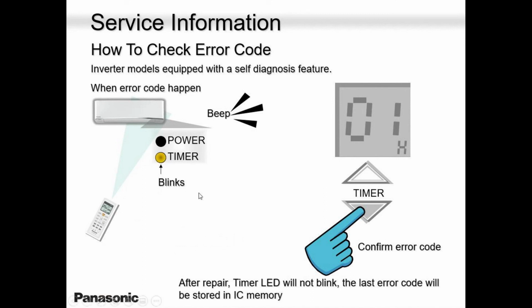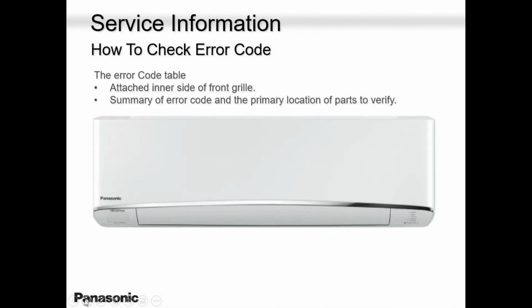While you're doing this, make sure you're facing the indoor unit, guys. Please don't forget that. You will see two dashes. With the timer up and down, either or, start scrolling. When you scroll, you keep going and going until the indoor unit beeps. When the indoor unit beeps, stop. Stop and look at the remote controller. You will see exactly what the error code is.